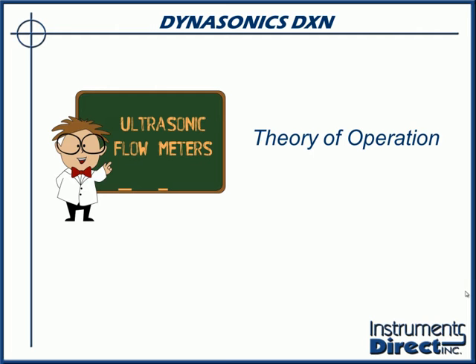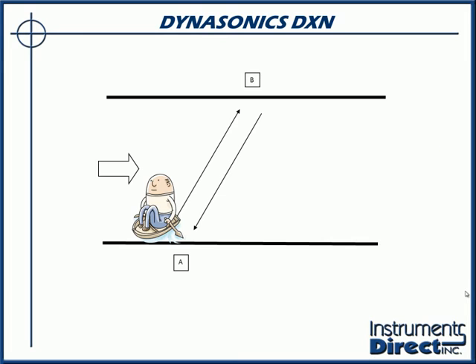One, we have an ultrasonic transit time flow meter, which is designed to work in ultra pure liquids, water, and sewage, but not sludge. So it works on clean liquids up to a couple percent solids by volume. In the same box is an ultrasonic Doppler flow meter. A Doppler flow meter is a device that works on heavy solids down to about 100 parts per million, 30 to 100 microns in size, and basically it works on sludge and sewage, but that's how clean it works. So how do these devices work in harmony? Well, first of all, let's break them in half.